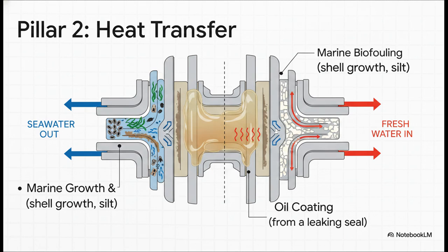Next is Pillar 2, poor heat transfer. In this case, your flow might be perfectly fine, but the cooler itself is failing. On the seawater side, you're fighting a constant battle with marine growth and silt. On the freshwater side, if your chemical treatment isn't right, you'll get scaling.